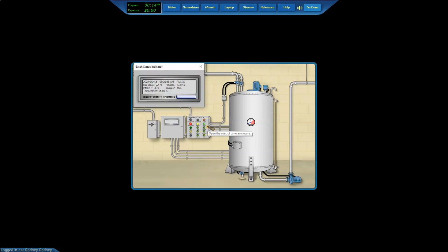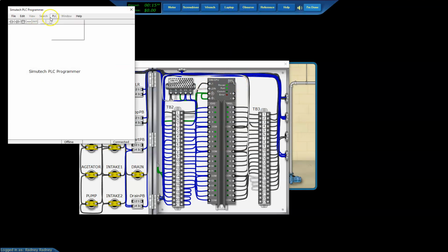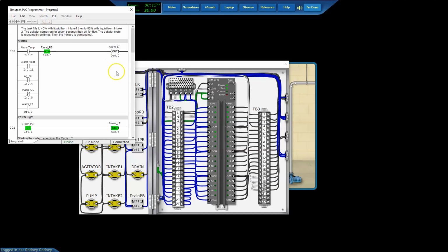So what would be your first step? I would go check the program and see what program 9 is supposed to do. Now, we messed with program 9 earlier. The question is, is it the same program, or would this be in a different simulation? What would we do? So we hook up our laptop to the PLC and go online. Right away, you should see an error here, and it is based off the feedback of the work order. So what error do you see?